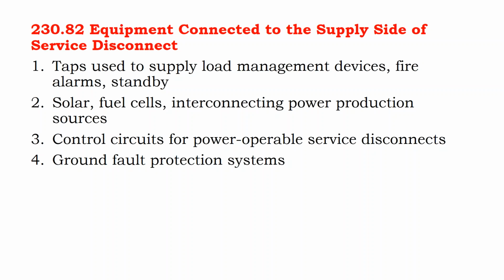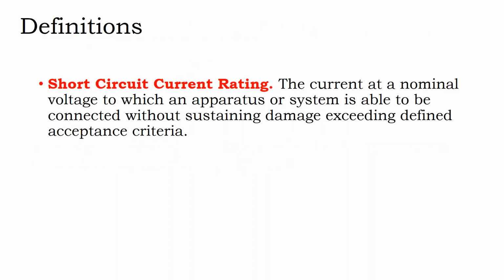And so if you can get them saying, well, yeah, we allow whole house generators to be connected through an automatic transfer switch, and you say, well, we're doing the exact same thing as that, all of a sudden they realize that their load side connection requirement is ridiculous, and you can start doing supply side connections in your area, even if you're the first to do it. So we've got solar being allowed to be connected on the supply side. It's really not that big of a deal to do supply side connections, and we've kind of talked through that already.